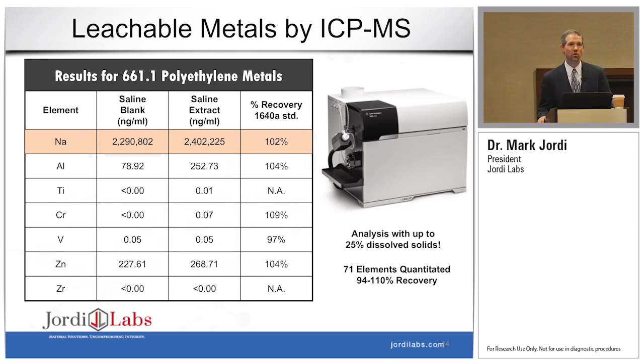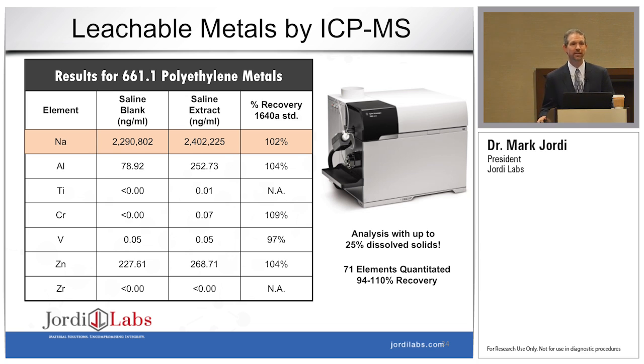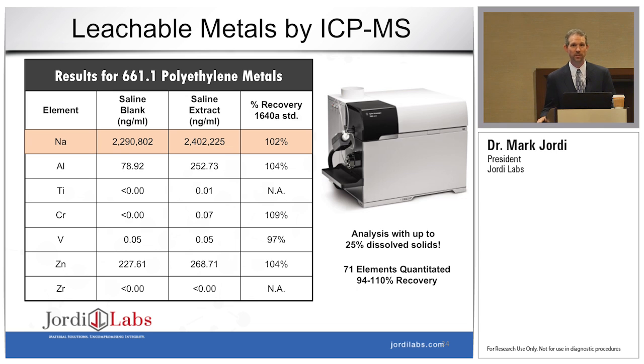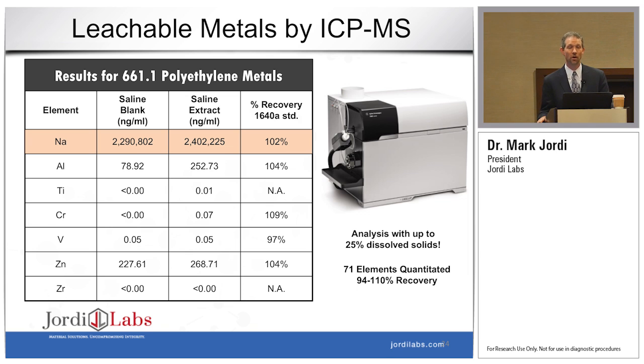In addition to 2D UHPLC, we've also been using the 7900 series ICP-MS systems because one of the most commonly used simulating solutions is saline, which can be a difficult matrix because of all the salt present. Because the 7900 series can use up to 25% dissolved solids, we can analyze these directly and still get to very low-level, PPT-level metals detection for a variety of analytes, even with all that salt present.